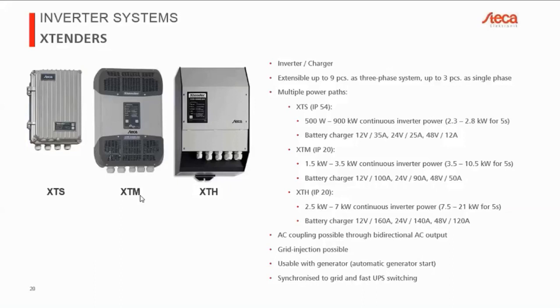And the other thing is the AC output of the Xtender is bidirectional. This is not the case for the SOLARIX PLI. So for example, you would not be able to connect a grid inverter to the AC output of the SOLARIX PLI. That would potentially just cause an error. There's an error for that on the SOLARIX PLI, but possibly even damage the SOLARIX PLI. For the case of the Xtenders, they have a bidirectional AC output, and this means that you can operate them with a grid inverter in what's called an AC coupling system. I'll explain that in a moment.